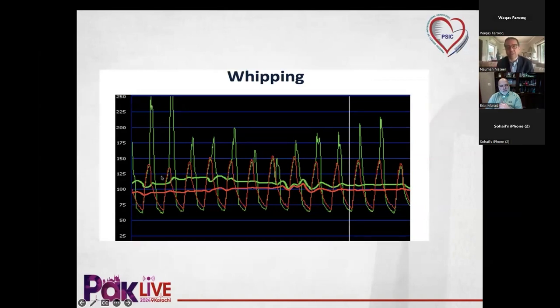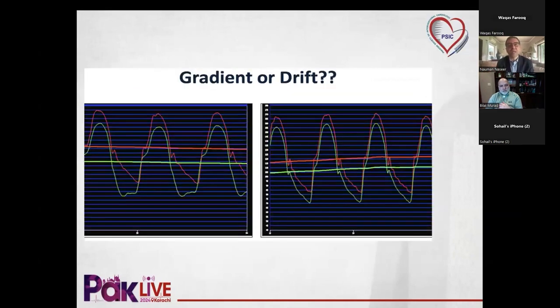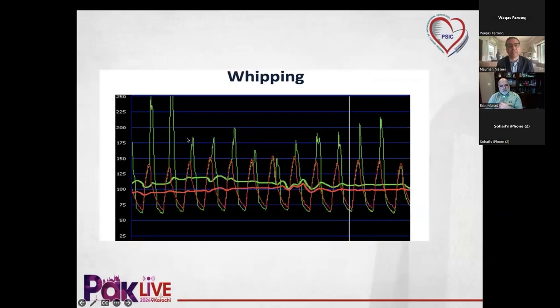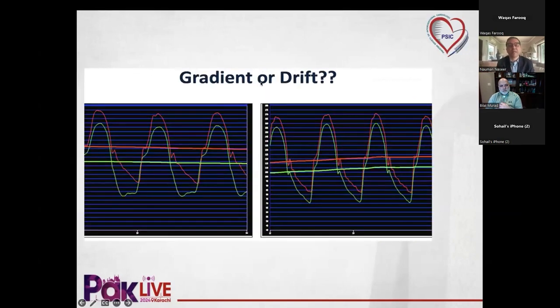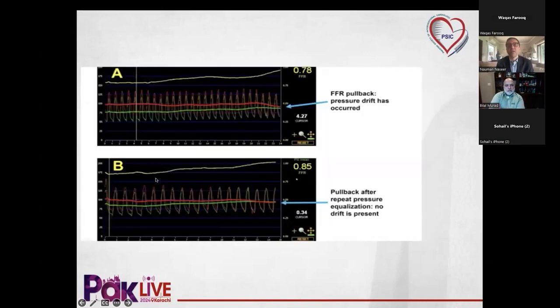So just treat just the distal tip of the wire. And the transducer is hitting the vessel wall in a small vessel, and because of that you're getting the whipping artifact. Which is the gradient and which is the drift? So this is the true gradient. If you're seeing the tracing of the distal pressure, this in green, exactly similar to the aortic pressure without some of this ventricularization that you see, likely this is the example of drift over here, and this is the example of true gradient. So FFR pullback, pressure drift has occurred over here.